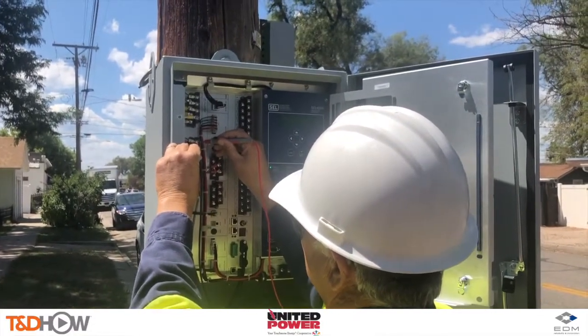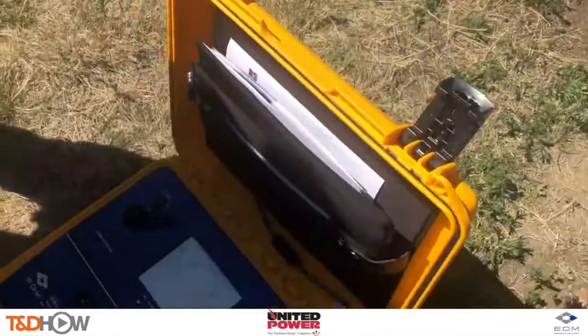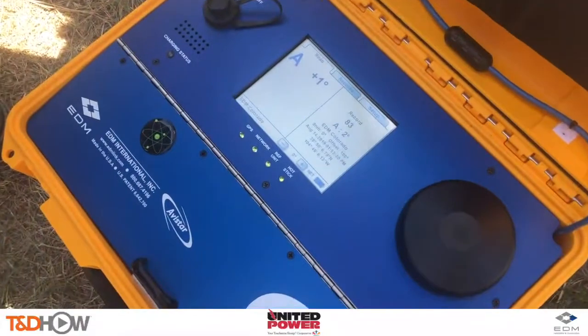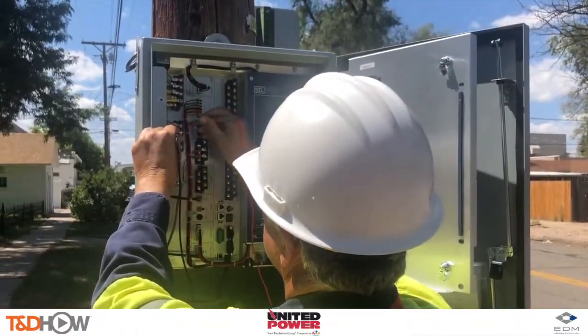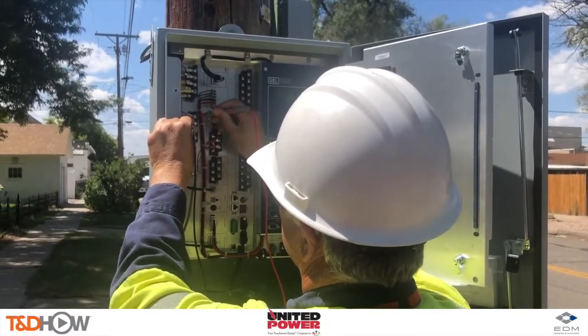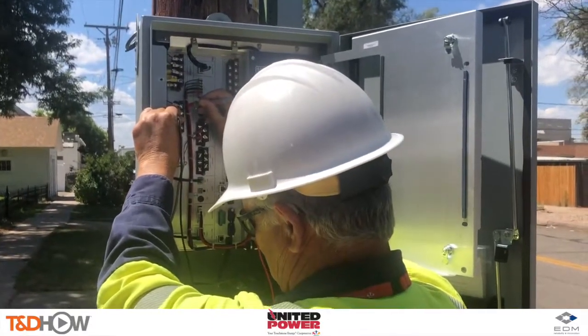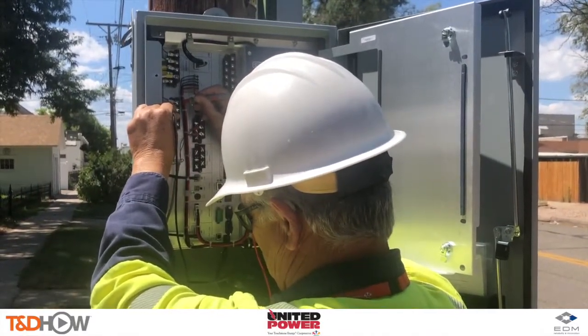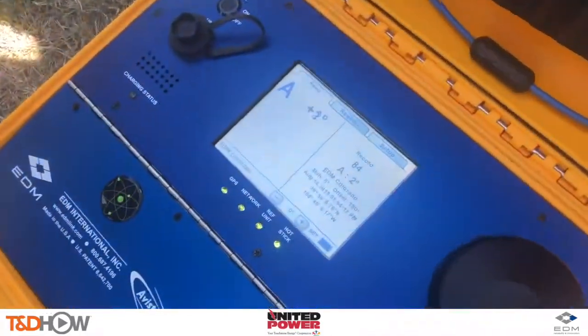In this application we ensure primary phasing matches recloser phasing. That way if there's a fault, we'll be able to trust the recloser control phase targets, and if there is low line voltage on one phase, we'll know it's reporting correctly. For more information regarding EDM's phase tracker line, visit their website at edmlink.com. I'm Jim Ducart with T&D How videos — thank you as always for watching.